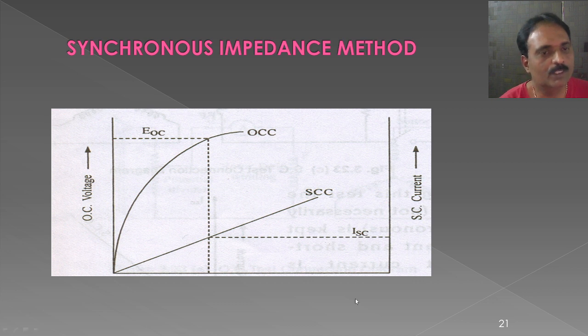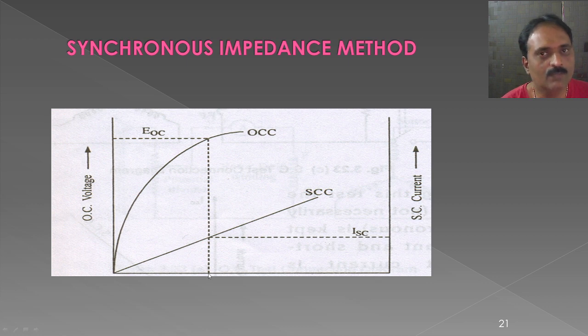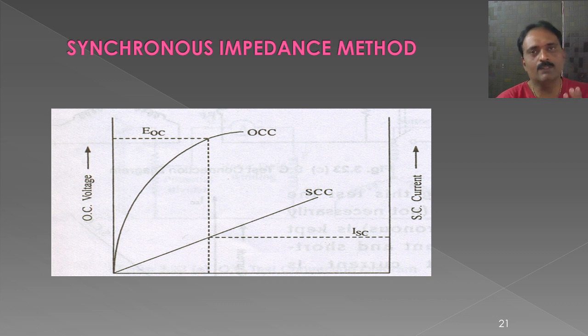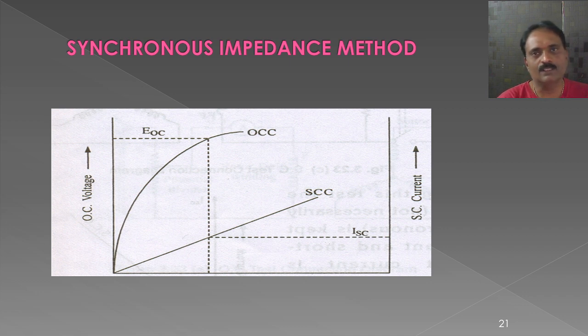The ratio of open circuit voltage to short circuit current for a given field current gives the synchronous impedance ZS: ZS = Eoc / Isc. Since we already know the armature resistance RA, we can find the synchronous reactance XS using the formula: XS = √(ZS² − RA²).